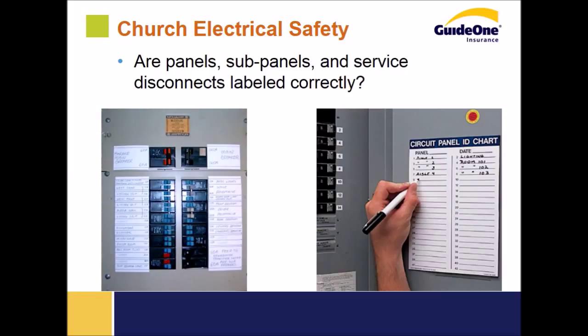Something else we'd like to see at our churches, and some of this has to do with lockout, tagout, and just knowing which switch to throw in the case of an emergency: we need to see that these panels are labeled, and that the breakers and mains are labeled properly, so that they can be de-energized in an emergency, and so that it's understood very clearly which equipment is operated by this switchgear.